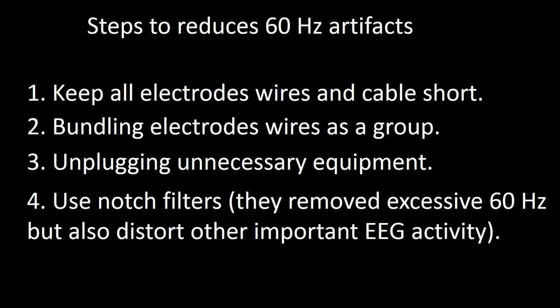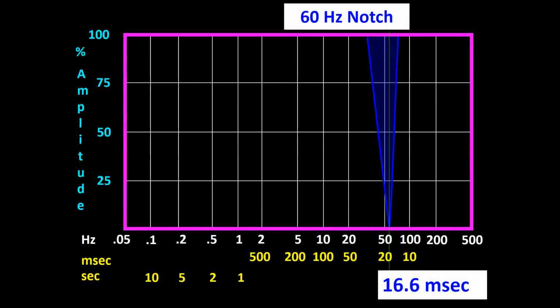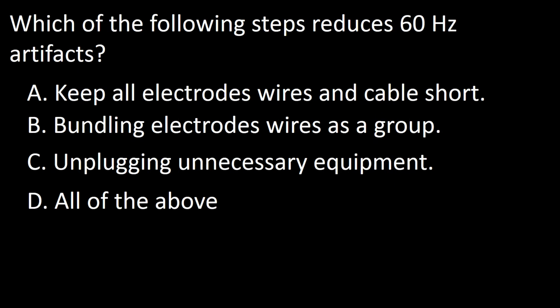The fourth step that we can take to reduce 60 Hz artifact is to use the notch filter. It is important to realize that using the notch filter will also distort other important EEG activities, and that not all 60 Hz notch filters are the same. Some notch filters have a very steep roll-off and as such will not significantly affect any activity other than 60 Hz activity, whereas others, usually those in the older machines, have a less steep filter, thus reducing the amplitude of waves even as distant from 60 Hz as 10 Hz and 100 Hz. So the answer to this question is D.